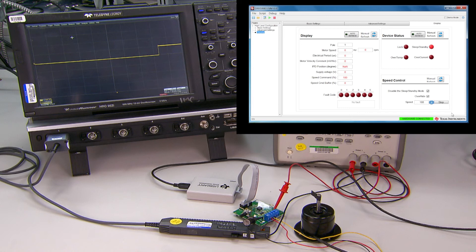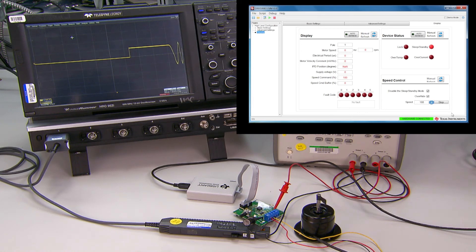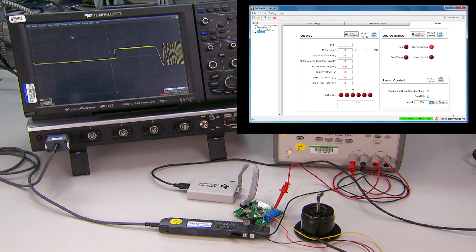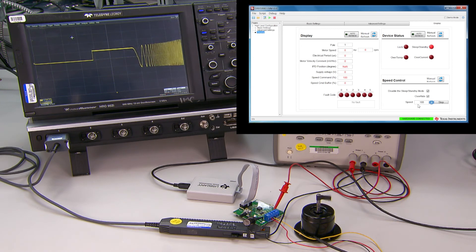By then, the current probe should pick up a sinusoidal current waveform with increasing frequency until the rotor frequency matches the open loop to closed loop threshold.